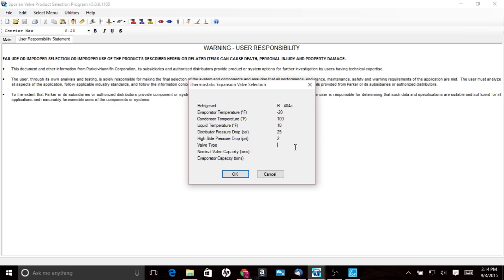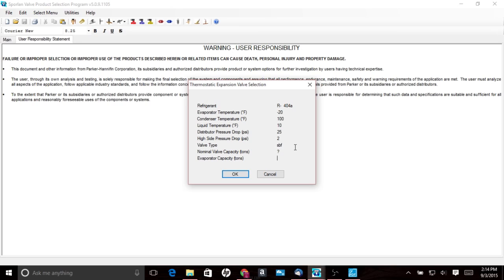So I'm going to first put in this information with the valve body that they had originally on the coil, or they still do have on the coil, which is an SBF. And we're going to put in, we're just going to skip over nominal valve capacity because we want it to figure out that information for us. And we're going to put in the evaporator capacity at three tons. Oh excuse me, and we're going to hit okay. And you're going to get this screen right here.